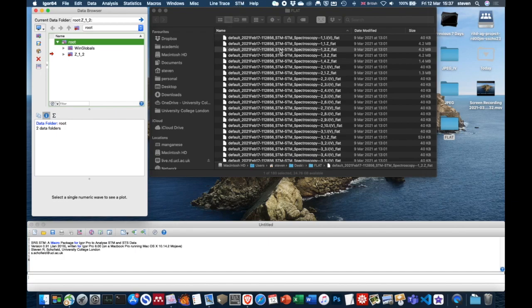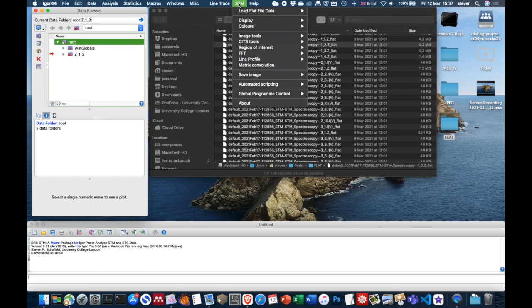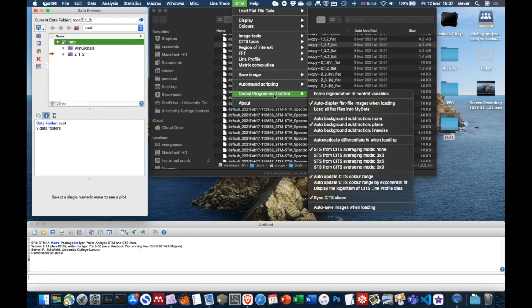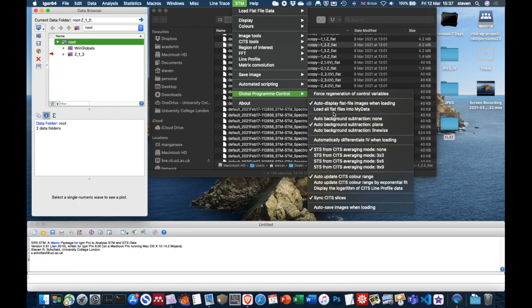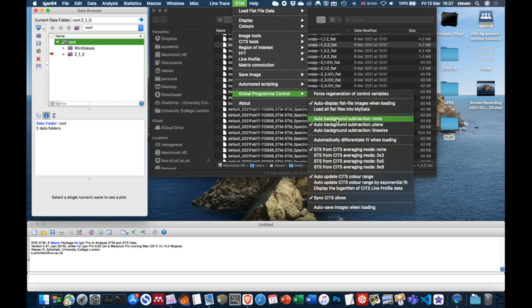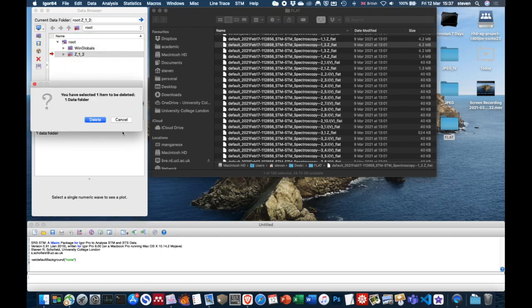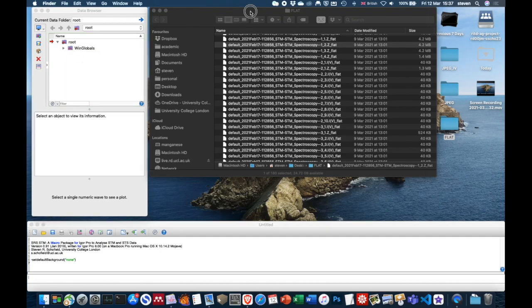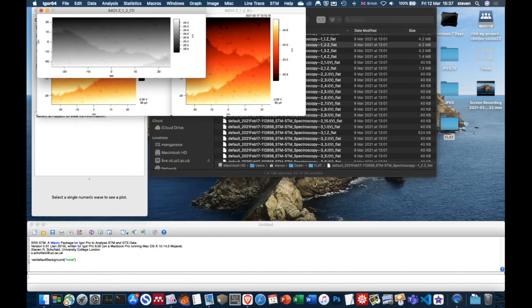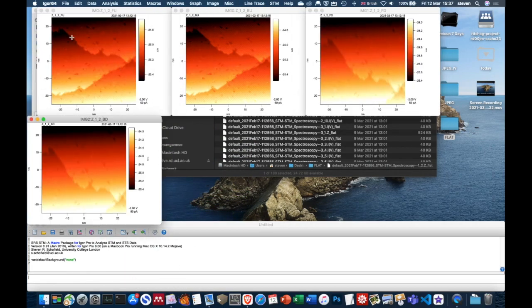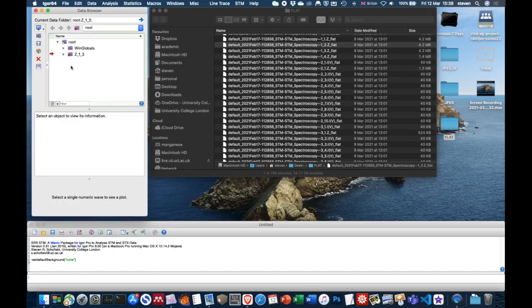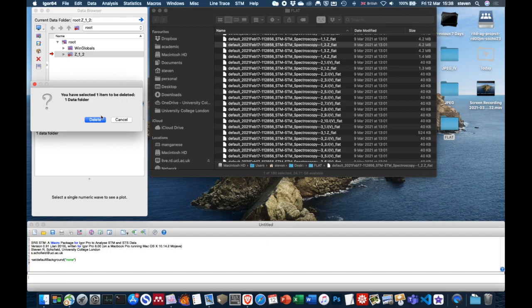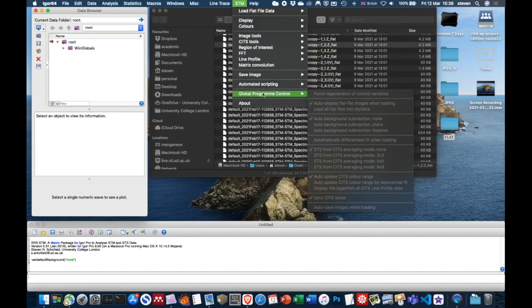But I do want to show one other thing about the topography images. And that is this way that we have for processing all of the data that's in your data folder. If you go back to the STM menu for my macro package, then this item here, global program control, allows you to set some options. These are all toggle switches here. So if I click on here, it'll have a little check saying that this is checked. At the moment, you see this says auto background subtraction plane. So if I were to make this auto background subtraction none, and let me just delete the image that we had there before. If I now load that image in again, this time you see it hasn't done the plane subtraction. So it's got, you can see there's this overall macro slope on the data.